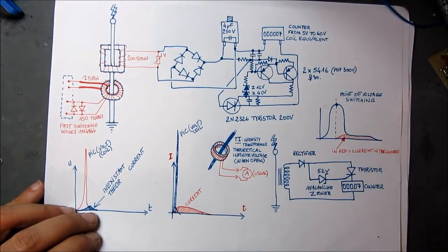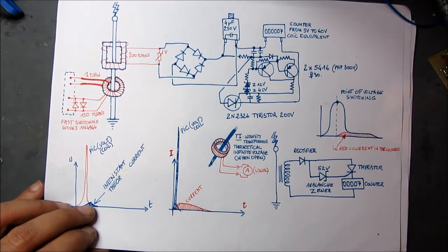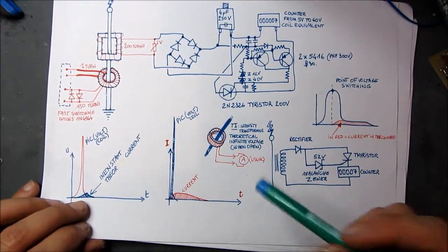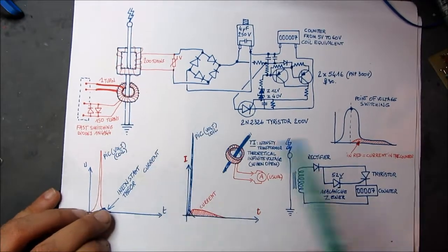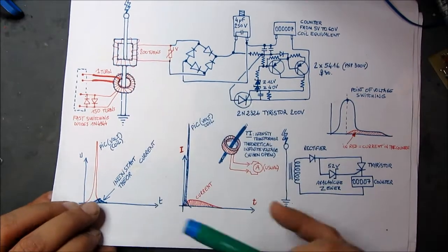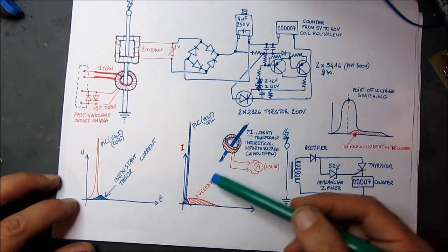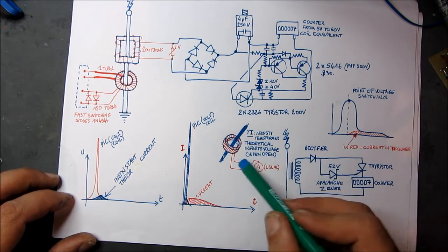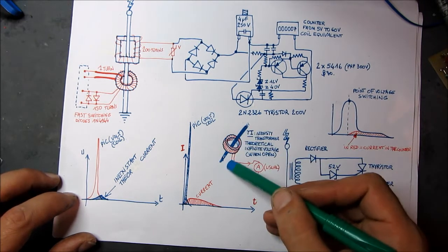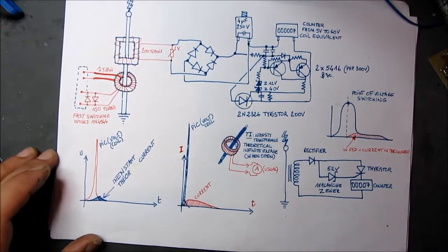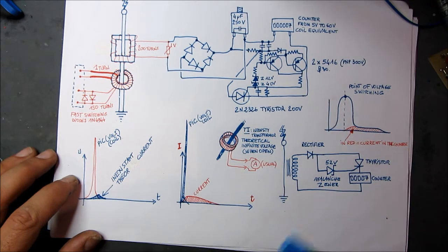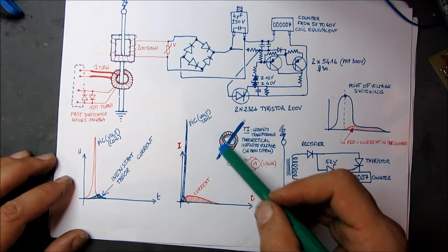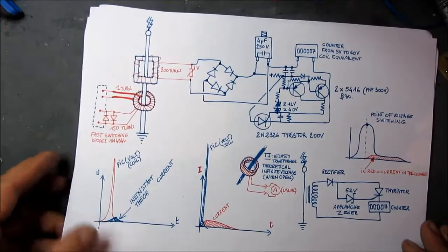What you need to know is that this clamp meter is actually what we call in French a 'transformateur de courant' or in English an intensity transformer. Theoretically, it has an infinite voltage at the output because this device is made to transform the current of one wire. Theoretically, when the loop is open you will have infinite voltage at the output — this is the reason why, in industry, manufacturers tell you that you must not leave the loop open, because it can destroy the transformer.